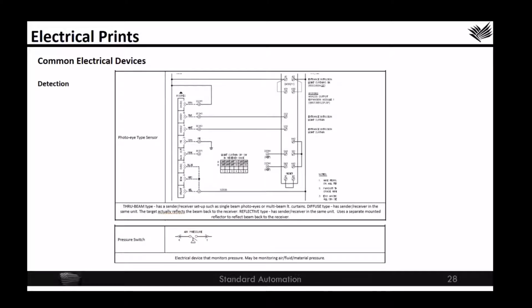We also have the photo eye type sensor. For the photo eye, you have the through beam type, which will be a sender and a separate receiver. So the sender will send a single beam, the receiver will receive it, and as long as the receiver receives every single beam, then the connection is made. You also have diffuse type, which are sender and receiver in the same unit. The target would actually reflect the sending signal back into the receiver. You also have a pressure switch, which would use a pressure mechanism to actuate a switch as opposed to a physical pushing connection like we would see in the limit switch or door detect switch. This would require a certain amount of pressure to close the electrical switch.